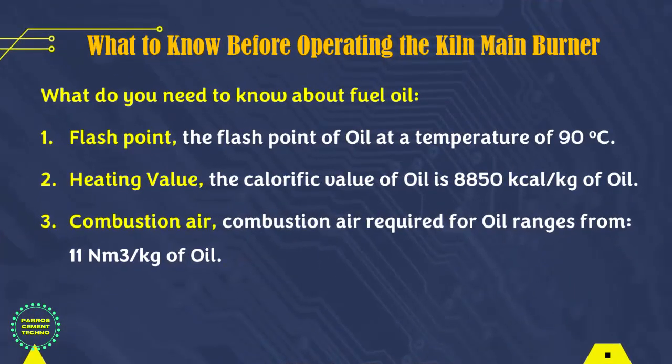Before operating the main burner there are several things that must be understood first. For diesel oil fuel: the flash point is at temperatures ranging from 60 to 90 degrees Celsius. The calorific value of oil is around 8,850 kilocalories per kilogram of oil. Combustion air required for oil ranges from 11 normal meter cubic per kilogram of oil, and air requirements are adjusted to fuel consumption.